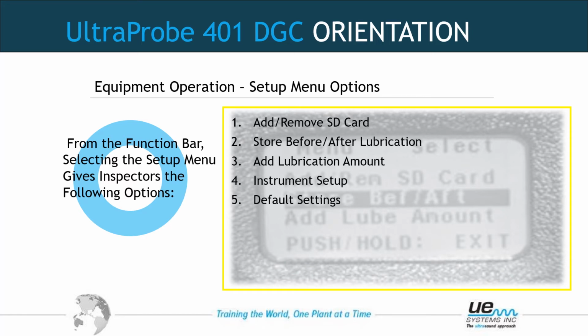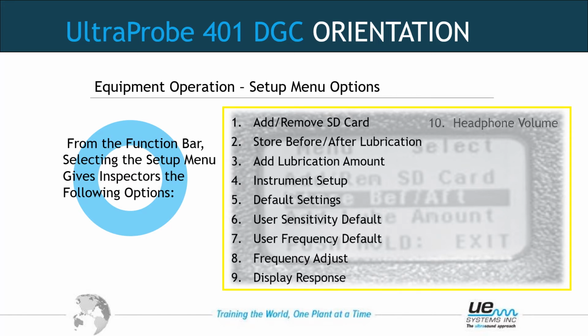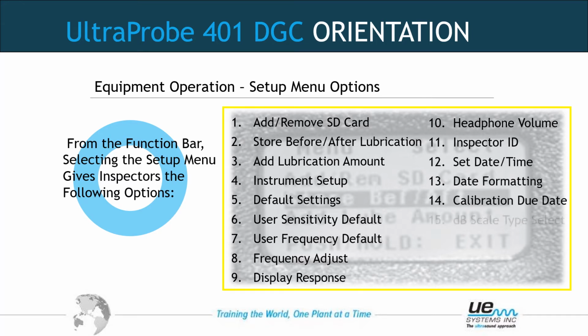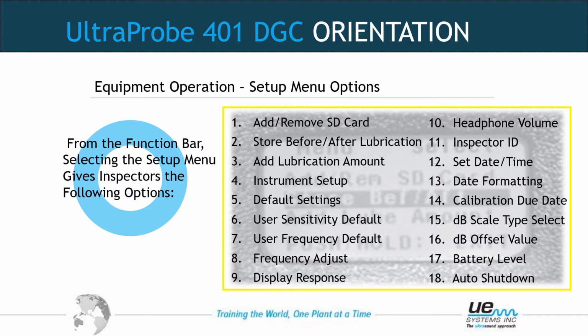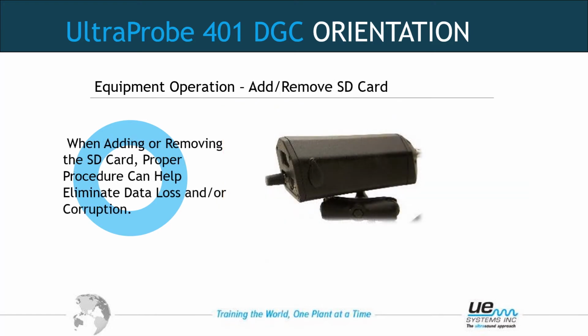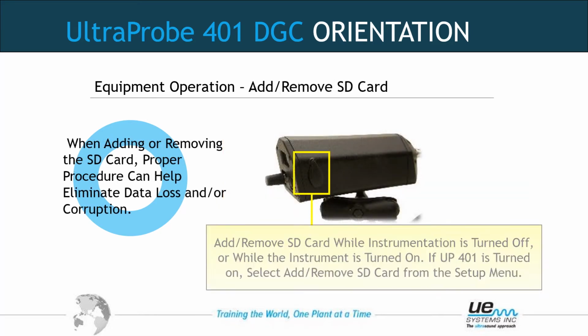To get into the setup menu options, you would again push the sensitivity knob until the function bar was flashing. Then you would rotate until you see setup menu and choose by holding down on the sensitivity dial just a little bit longer than normal, and you will come into the setup menu. These are all the items that we're going to cover. The first thing is add remove SD card. So once in the setup menu, it will say add remove SD card as the first menu item.